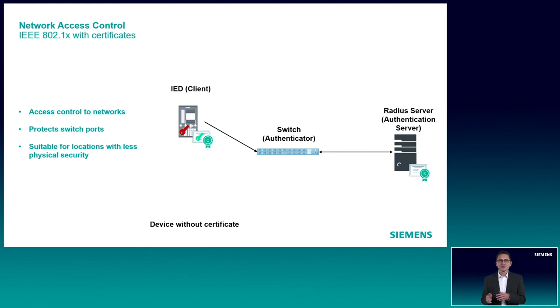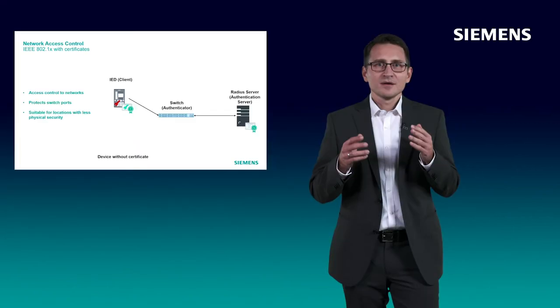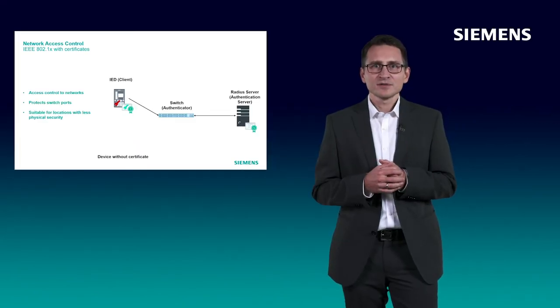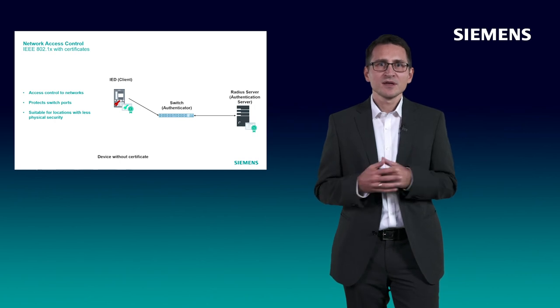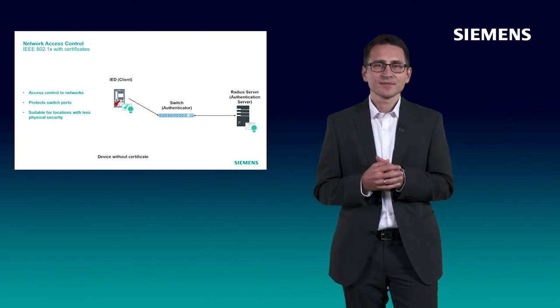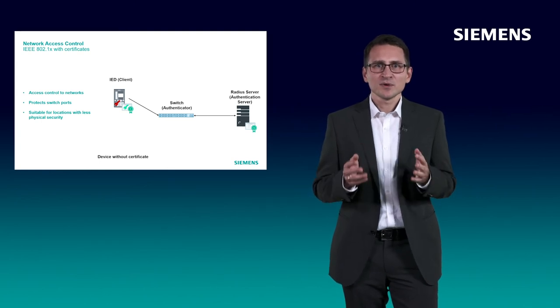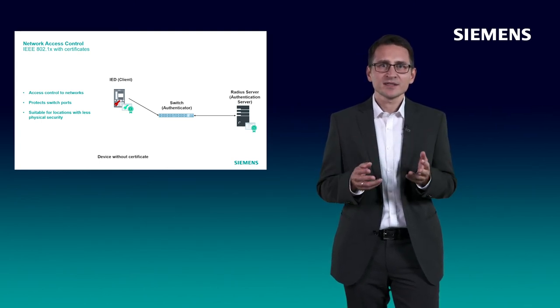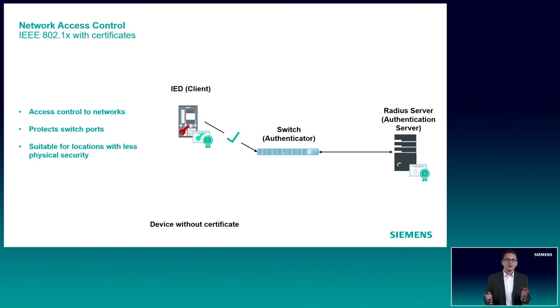During startup of the IED, it sends an access request with the client certificate. The switch forwards this request to the RADIUS server, and the RADIUS server checks if the client certificate and the access request are valid. The RADIUS server provides feedback to the switch that the authentication was successful, and the switch will grant access to the network. Only the IED with the corresponding private key will be granted access by the RADIUS server. In a scenario where someone unplugs the IED and connects any device without a valid certificate instead, it will not be able to connect to the network. The whole process happens automatically without any user interaction.